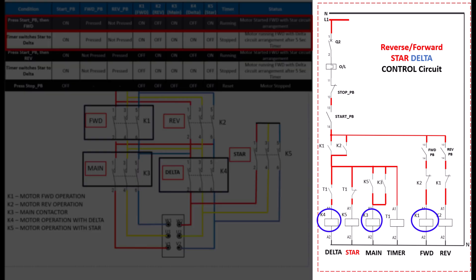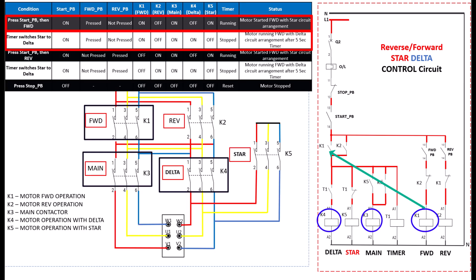Look at the control circuit. It has an interlock that ensures K3 main contactor and K5 star contactor engage only when K1 forward contactor is energized. If the motor direction is not selected, the motor will not start, ensuring proper functionality and safety.